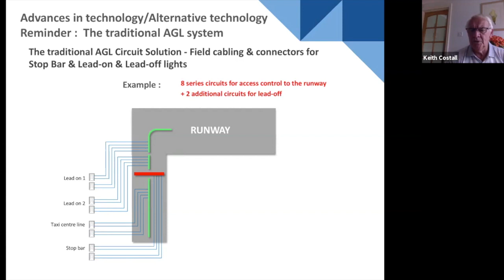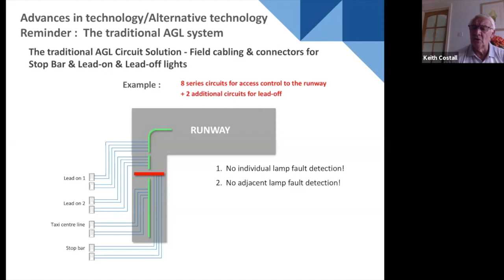For every system we must have a minimum of 2 circuits. So lead on, taxiway centerline, and stop bar are all dualed up. When you look at the number of circuits, you get 8 series circuits plus 2 additional circuits for the lead off capability, because lead off and lead on lights have to be operated separately. That's a lot of circuits. There's no individual light control and monitoring, and no adjacent lamp fault diagnostic systems built in. So that's a lot of circuits, cable, connectors, transformers, etc.